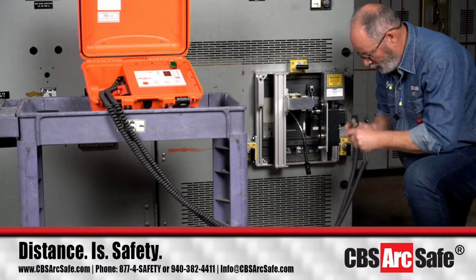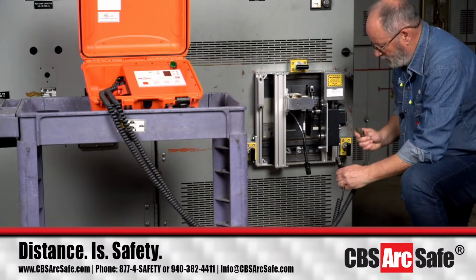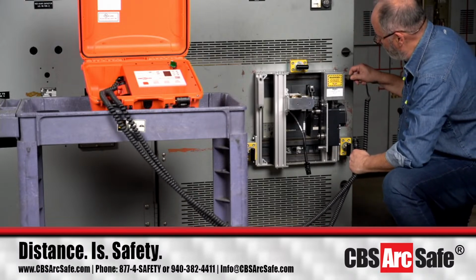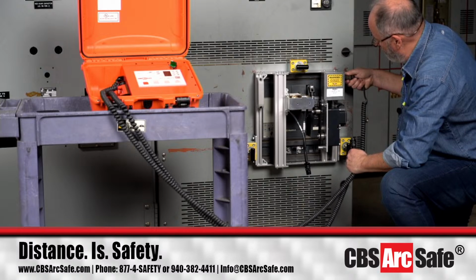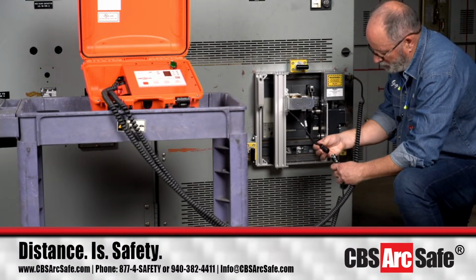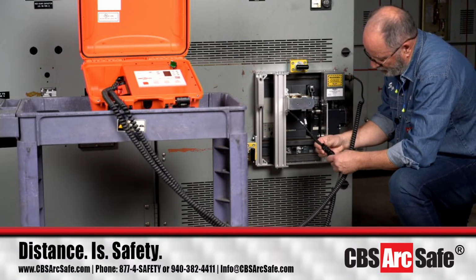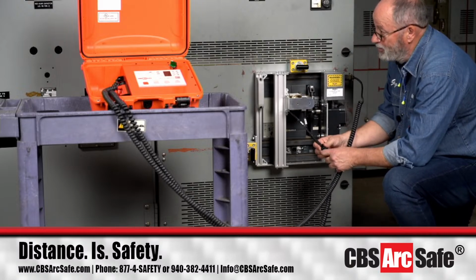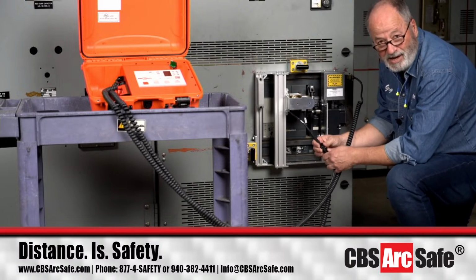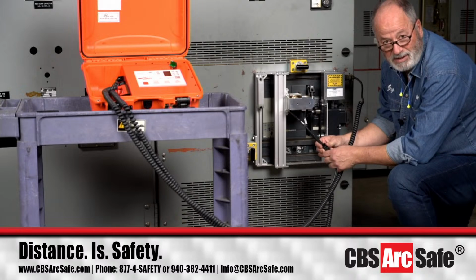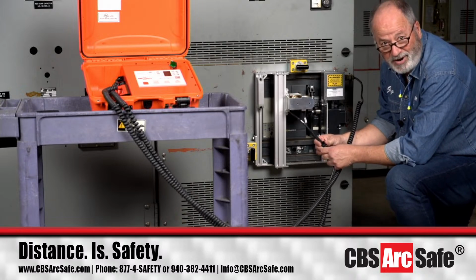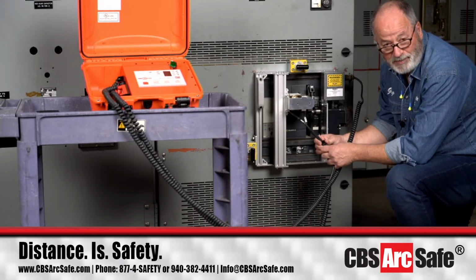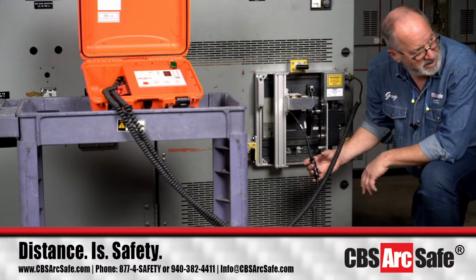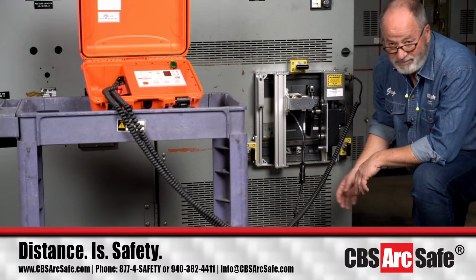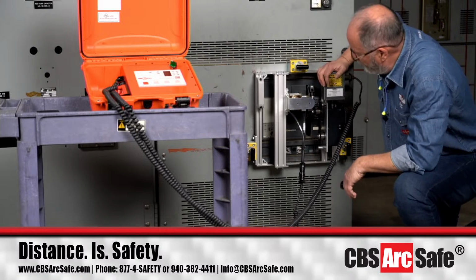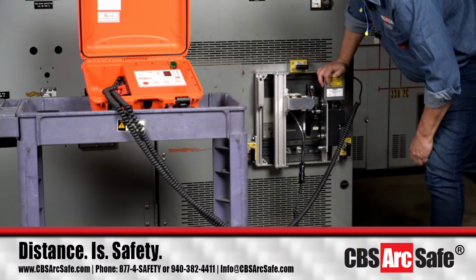I've seen data centers in the Dallas-Fort Worth area with double-ended subs and 5,000 amp Magnum DS breakers, and also 5,000 amp Masterpact breakers on them. The breakers you're not seeing, that you may also see, if you've got big things like the RJ frames for Square D, or the R frame for Cutler Hammer with the 2,500 amp breakers, we've got the ArcSafes for those also.